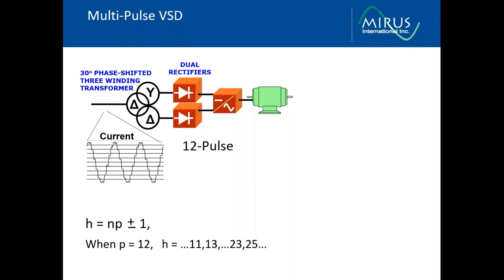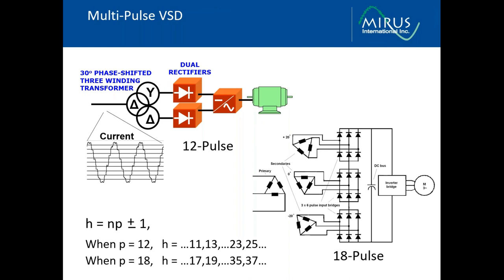There's always residual harmonics due to phase shift anomalies, power system conditions, voltage distortion, voltage imbalance, and so forth. But in theory, the harmonics that would be present are the 11th, 13th, 23rd, and 25th. In an 18-pulse application, we'll have three rectifiers supplying the inverter. These are phase shifted by 0, plus 20, and minus 20 degrees, and the resultant harmonics would be 17th, 19th, 35th, and 37th.